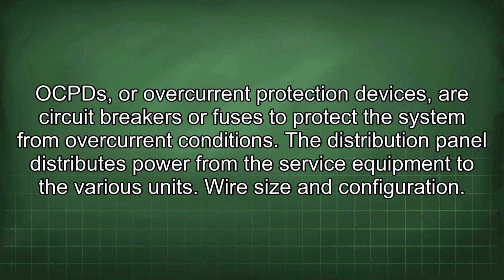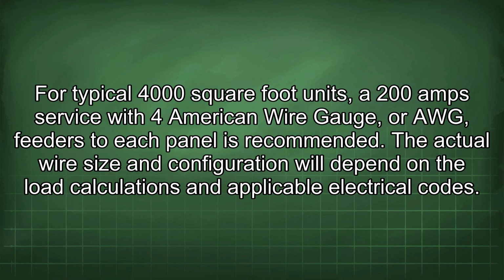Wire size and configuration. For typical 4,000 square foot units, a 200 amp service with 4 American wire gauge, or 4 AWG, feeders to each panel is recommended. The actual wire size and configuration will depend on the load calculations and applicable electrical codes.